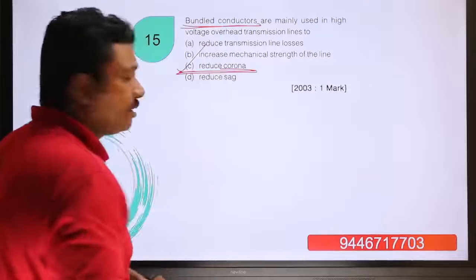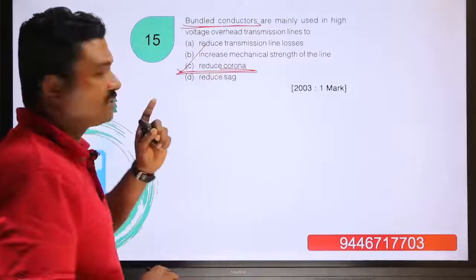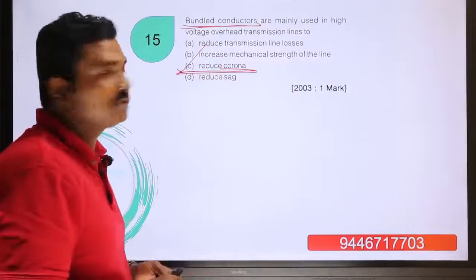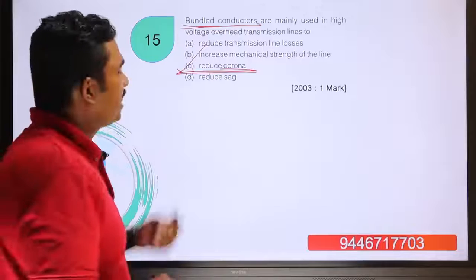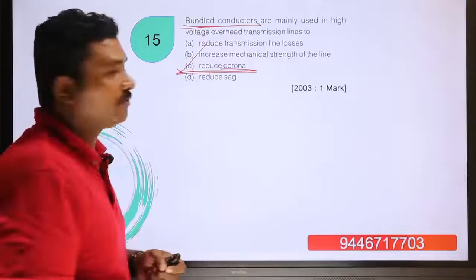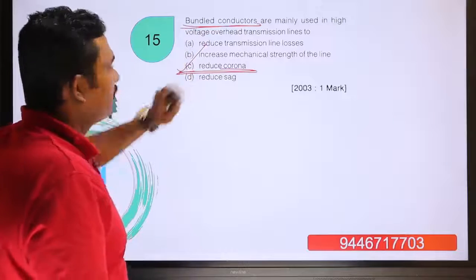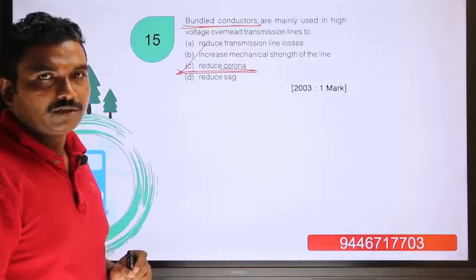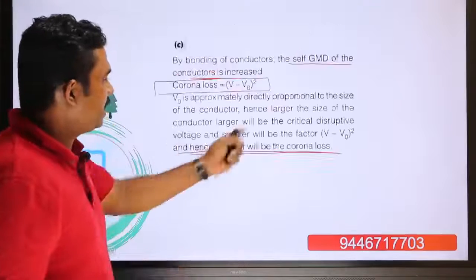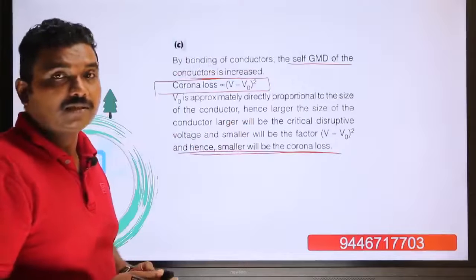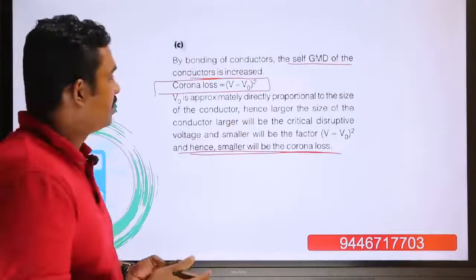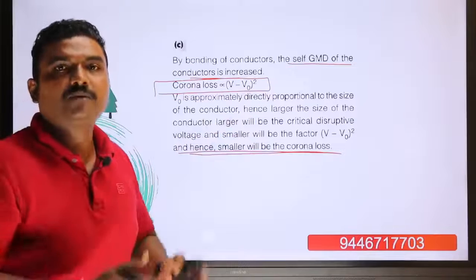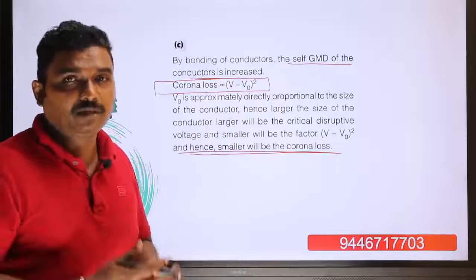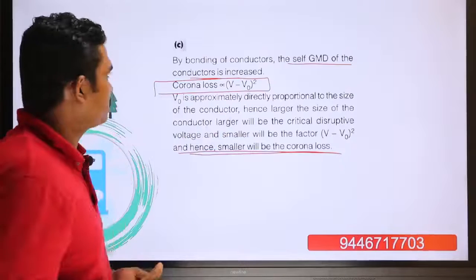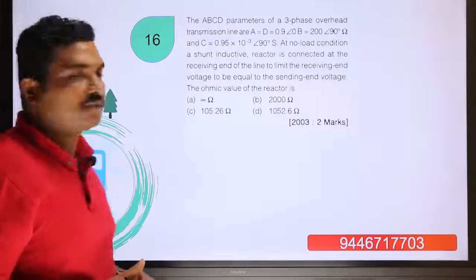Bundle conductors are directly discussed in the theory as a factor to reduce corona, so you should review the theory portion covering the advantages and disadvantages of corona, the factors affecting it, and methods to reduce its effects. Bundle conductors are one of the biggest methods to reduce corona—using them increases the effective radius of the conductor system, which increases the critical disruptive voltage and thereby reduces the chance of corona occurring. Now moving to question 16.